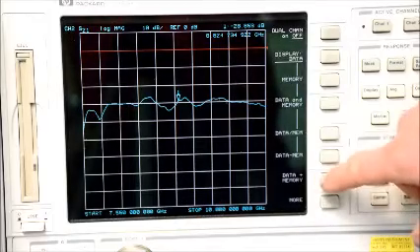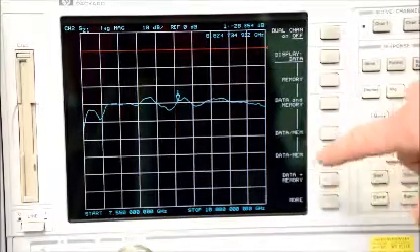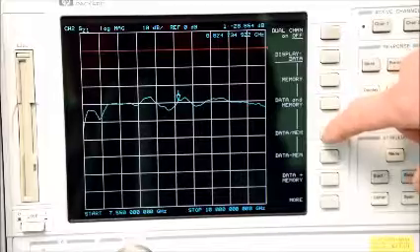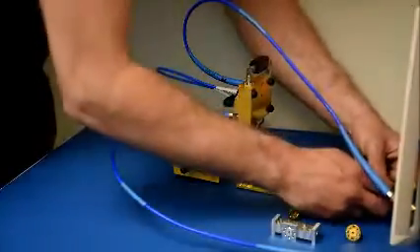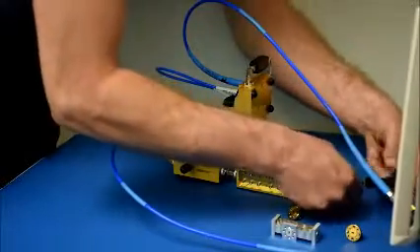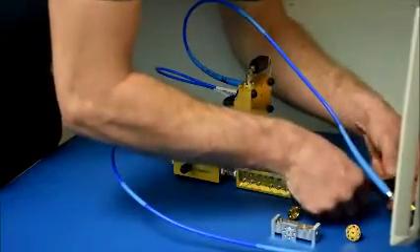We'll commit the data to memory, and then we'll use the data over memory function to zero out the system. Now that the system is calibrated, we'll remove the short from the output port of the directional coupler.